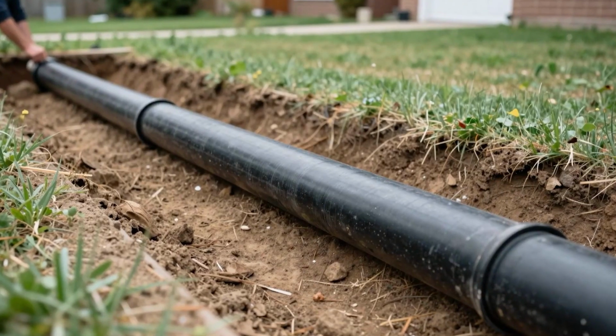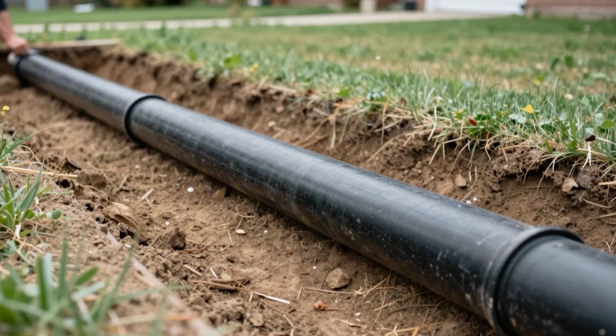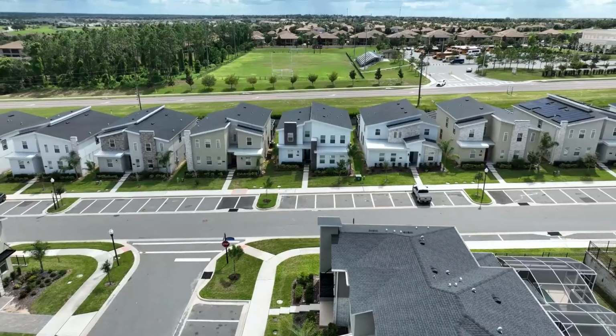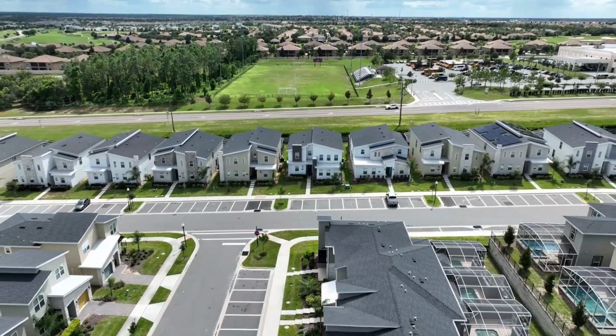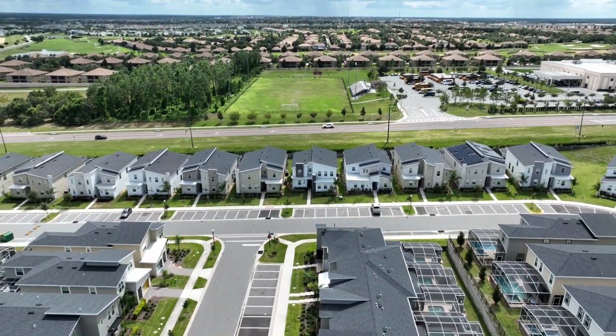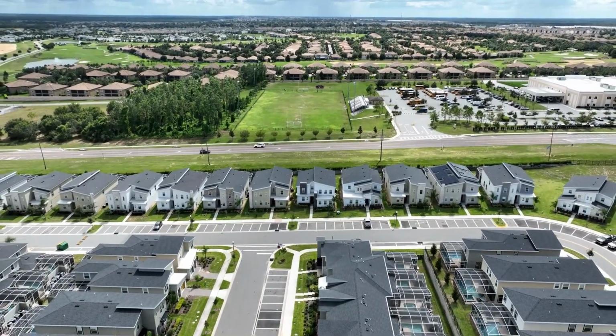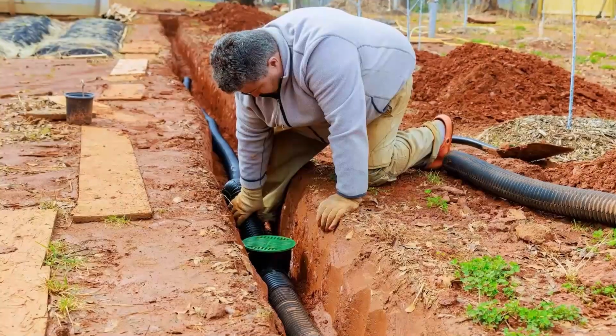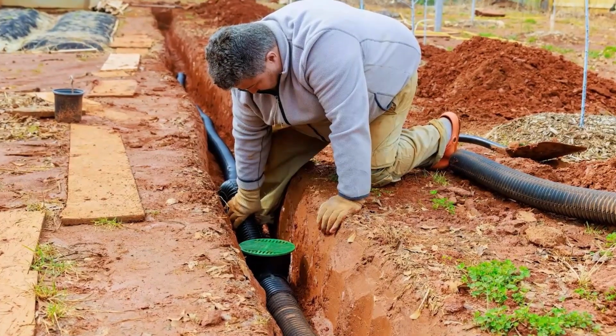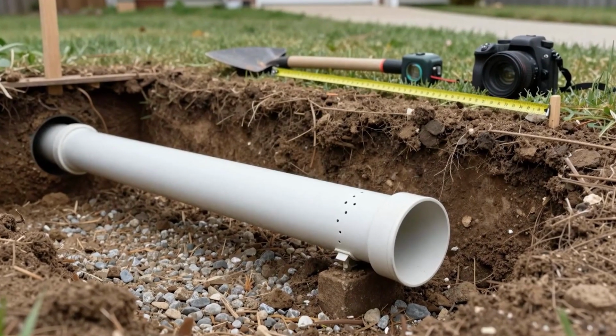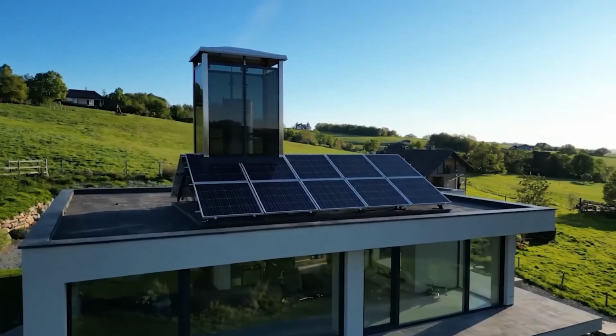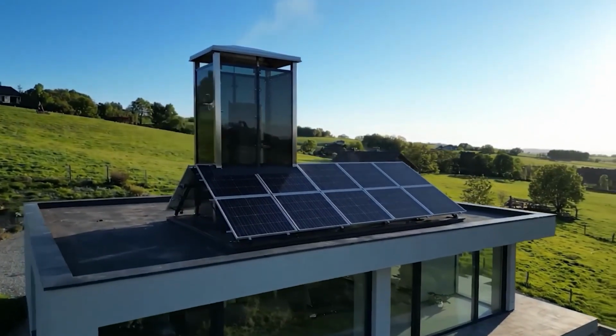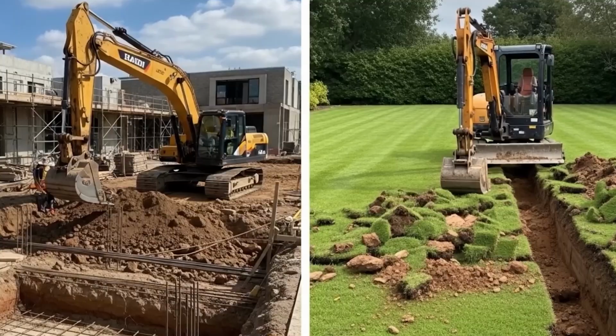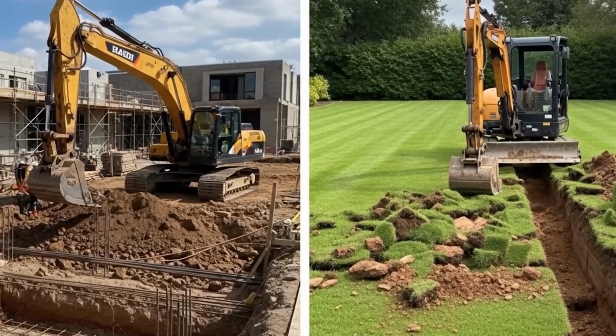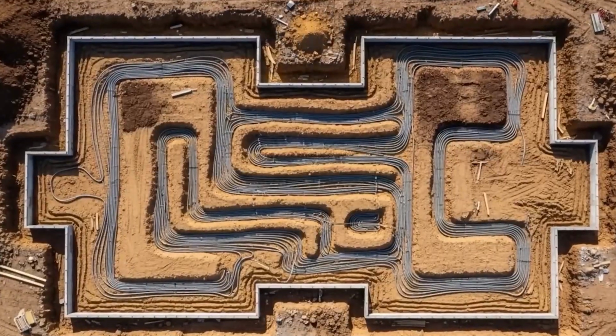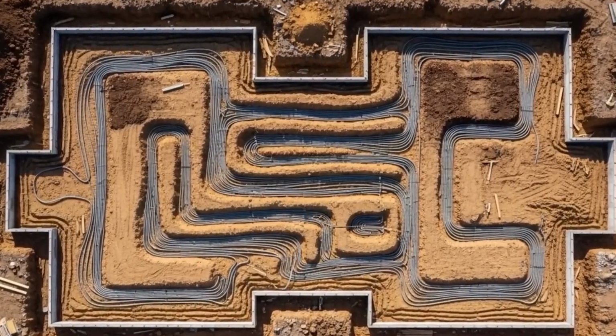Practical implementation. Here is what an earth tube installation actually looks like in practice, and what it will cost you. For a standard 1,500 square foot home in a hot climate, the recommended configuration is a single run of 6-inch smooth bore HDPE pipe, 100 feet in length, buried at a depth of 6 feet. The inlet should be positioned on the shaded, north-facing side of the property, elevated slightly above grade with a fine mesh insect screen and a coarse particulate filter. The pipe should slope very slightly, around 1% grade, toward a low point where a condensate drain can be installed before the pipe rises into the building.